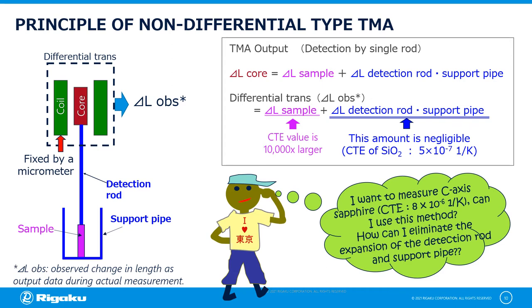On the other hand, if you want to measure a material with a very low thermal expansion, such as C-axis of sapphire with a CTE value of 8 × 10⁻⁶ per Kelvin, then this method cannot provide an accurate result. In this case, the differential type TMA is an effective means.